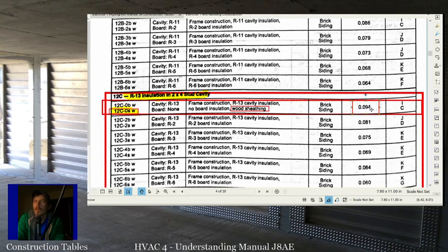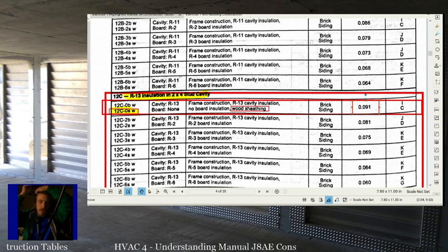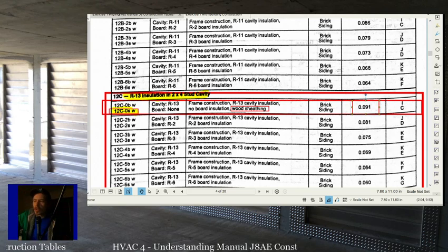It's 0.091. Commonly, your walls have one of the lowest U values of most of the components you work with. So like I was telling you guys the other night, that's the one where, if you're going to get it wrong, if you're not going to have the exact value, even though there's a lot of wall, it'll still have one of the lower impacts on your load calc. So if you're not sure if it's R11 or R13, it's safe to say it's just R11. You know what I mean?